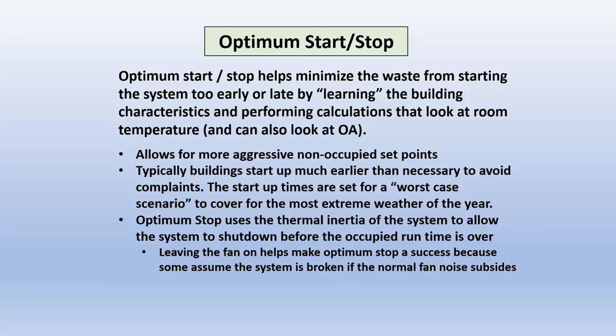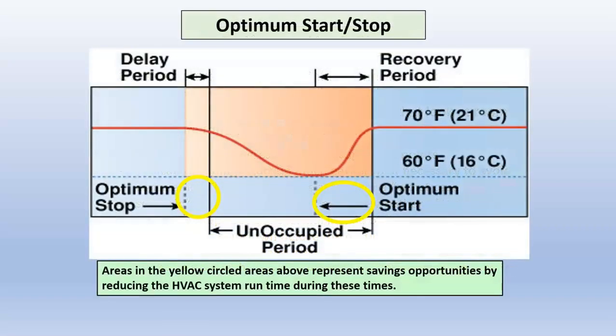And sometimes airflow has quite a bit to do with comfort. Sometimes when the airflow is shut off, people may say they're uncomfortable. So you can try Optimum Stop and shut everything off, but if that doesn't work, just turn the fan on. There's a nice little graph of Optimum Start and Stop. You can see these windows here. These are the savings opportunities where I used to start way back here. Well, now Optimum Start and Stop is going to figure out where I'm going to actually start, so I don't have to start way back here. My recovery period is going to be adjustable and change based on the needs of the system.